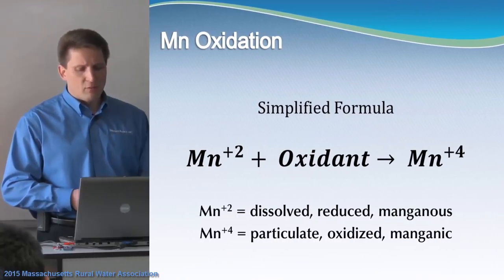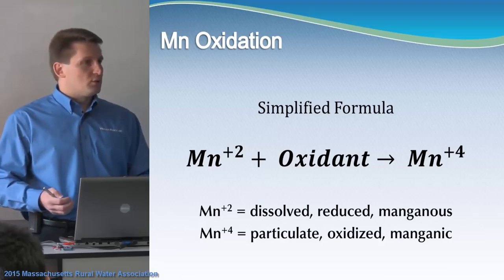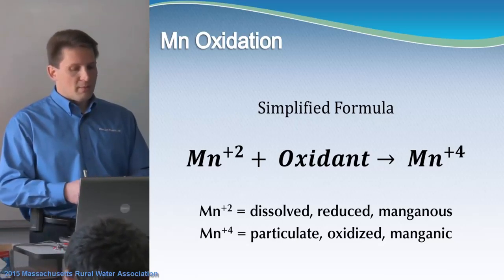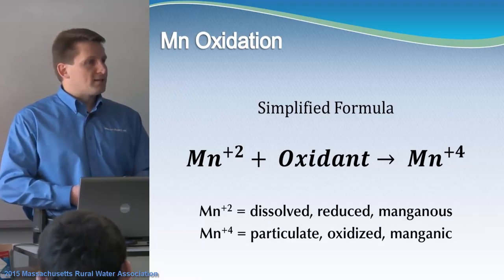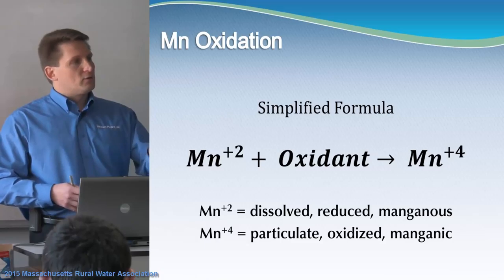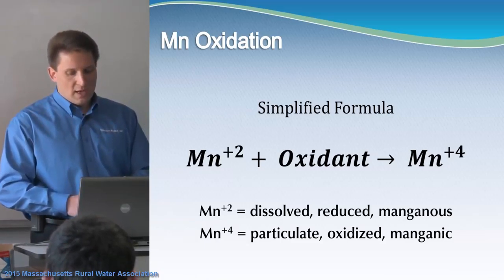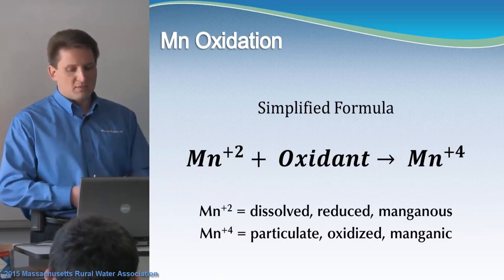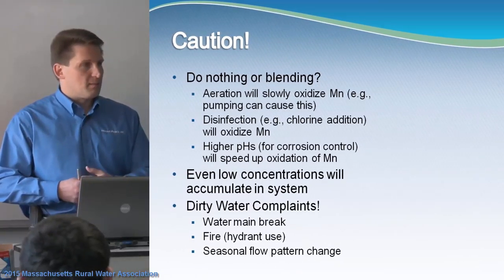Here's a simplified formula for manganese removal. On the left you have Mn²⁺ — dissolved, reduced manganese. You mix that with an oxidant such as chlorine or air, and that transfers it — removes a couple of electrons — bringing it into the particulate or oxidized Mn⁴⁺ state so that it's actually removable by a filter.